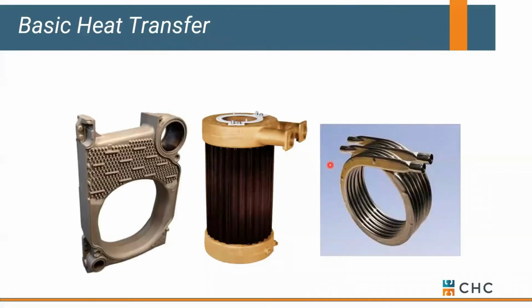Now, when it comes to a boiler, we have different materials that we can use for transferring that heat. Old school might be a cast iron sectional. You might also have some copper fin as a viable option. More commonly, you're seeing a lot of stainless out in the marketplace. The one that's not shown, that I'll give you an example of in a minute, is steel tube. That's another option for materials. They all have different properties. They all have different resistance to condensing or non-condensing operation, low pHs, if you will. We'll talk about all that as we go through here, okay?